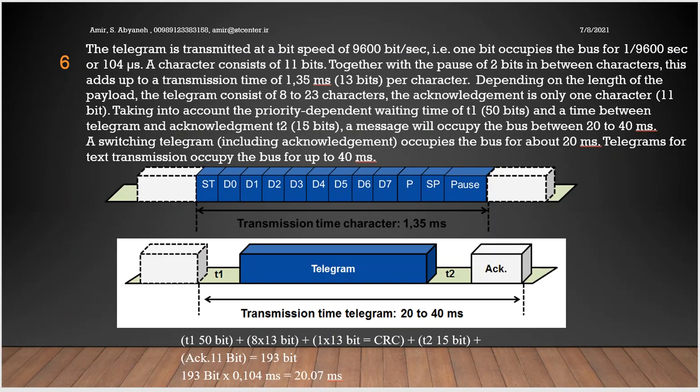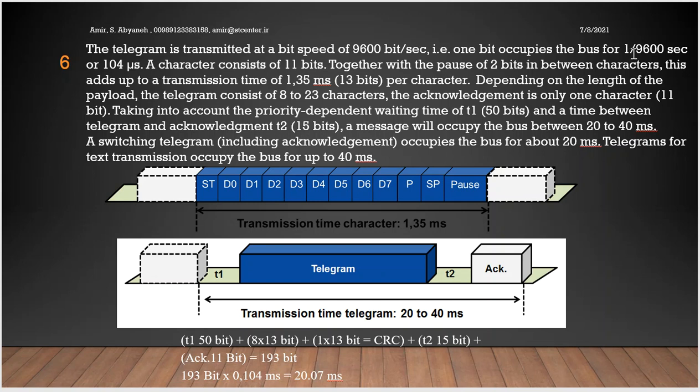The telegram is transmitted at a bit speed of 9600 bit per second. It means 1 bit occupies the bus for 1 divided by 9600 seconds or 104 microseconds. A character consists of 11 bits. Remember that a character consists of 11 bits. Together with the pause of 2 bits between characters, this adds up to a transmission time of 1.35 milliseconds per character.